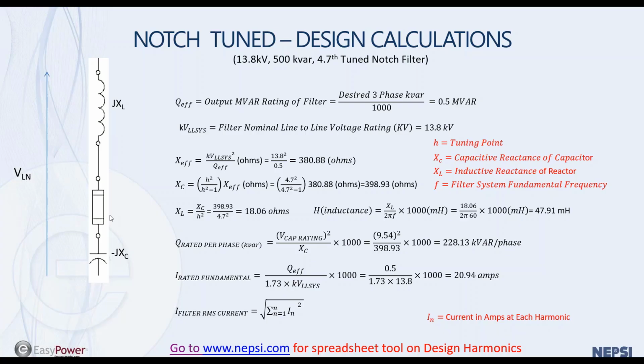So you have to come up with a Q effective value, put this harmonic filter design into your EasyPower analysis model, and then evaluate the amount of harmonic current that actually flows through X of L and X of C, and evaluate that against the standards. The reactor is a custom built device, whether it's medium voltage or low voltage. It tends to be that in low voltage systems the reactors are a standard off the shelf design, and they do have a limit in their rating. So you have to evaluate how much current flows through that reactor versus its rating. And the same will be true for the capacitor.